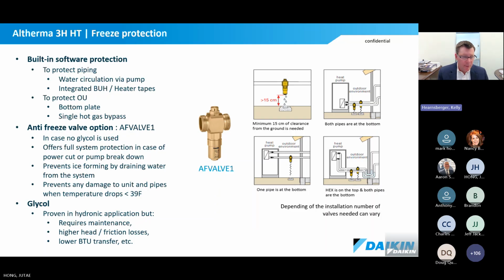And then in the event that you do lose power, we have antifreeze valves that trickle, we'll call it. They would trickle a little bit when we get close to freezing, 36, 38 degrees, they're typically set. And then they would prevent the pipes from freezing because you still have a little bit of water flow. In the event that that's not acceptable to a homeowner or your build practice, you can use glycol in this system. It's a closed loop system with a double wall protection against the domestic hot water. So you could run glycol. It does come with a little bit of a performance derate, but I think that's common. Most people understand that, even with boilers. So there's multiple options. We encourage people to design properly, just use common sense on the design practice, and likely you don't need to have a lot of extraordinary efforts, even in colder climates.